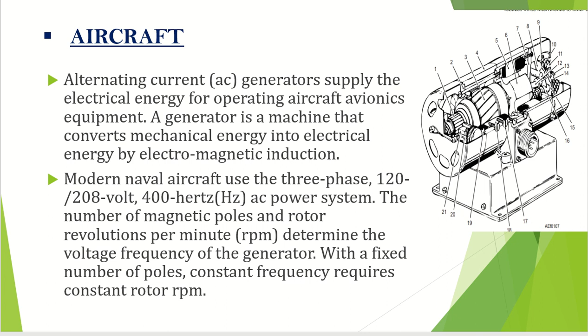We will see this is the armature. The mechanical energy is converted to electrical energy. The 120/208 volt three-phase AC power subsystem has many advantages over the 28-volt DC system. It requires less current than the 28 volt DC system because of higher voltages and a ground neutral system. The current required is a fraction of that required for the same power in a 28 volt DC system.